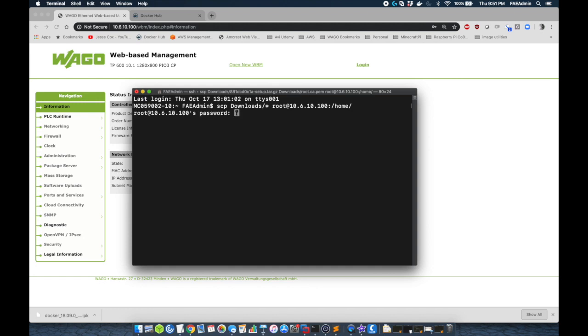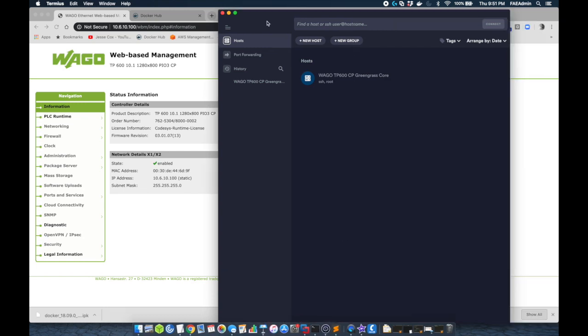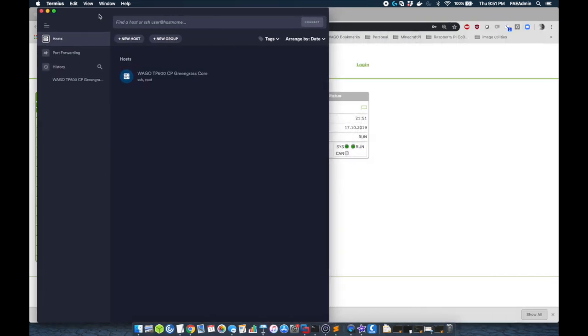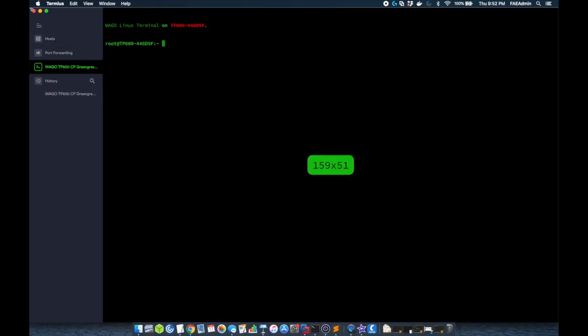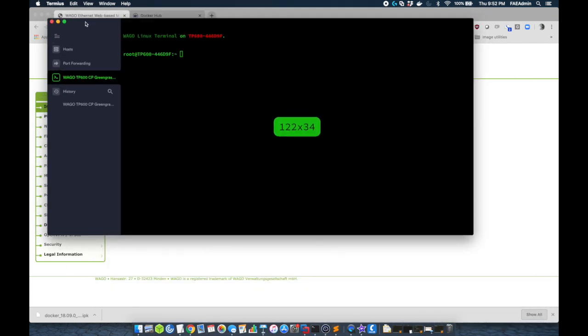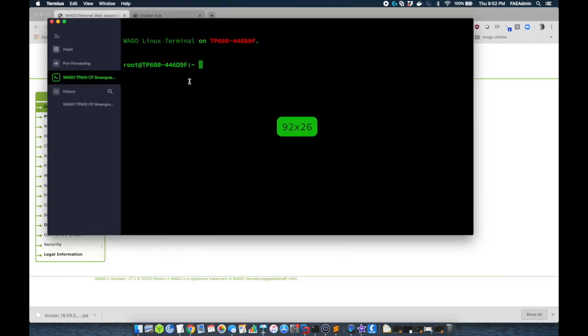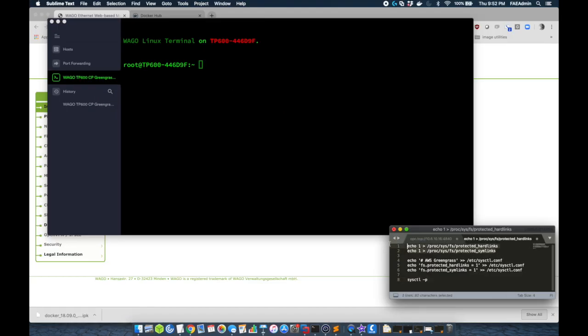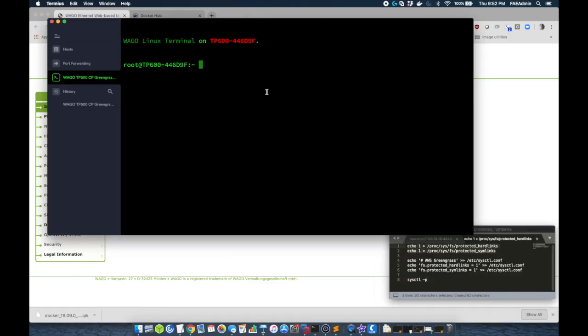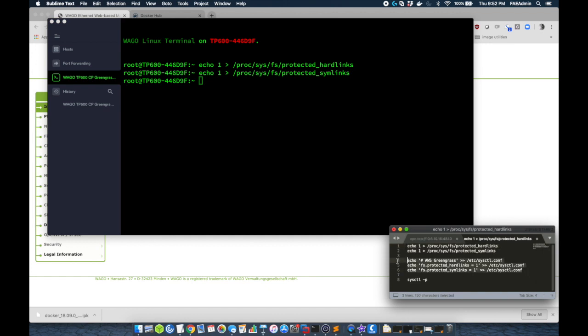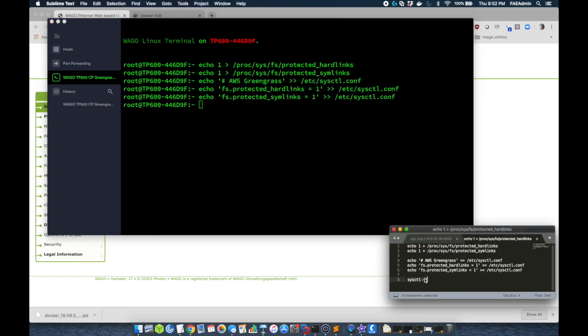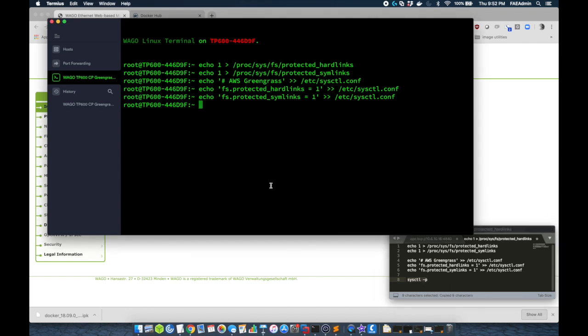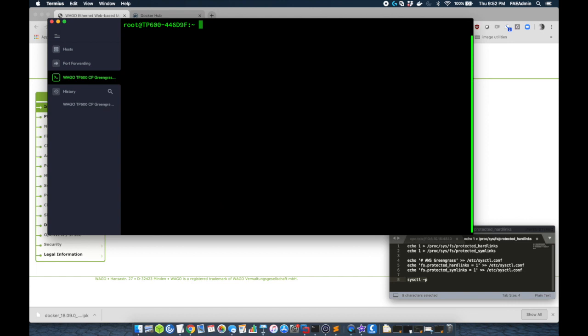Once these are copied over, I'm going to open up an SSH session with the PLC. We'll log in here using the WAGO root. I advise changing your root password on the shell. And I've got some scripts here that I'm going to use to create hardlink and symlink protection. The first set is going to create the protection. The second is going to make it stick through reboot. And then if you do the system control dash P, you can just verify those changes.